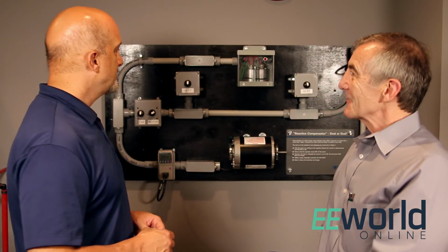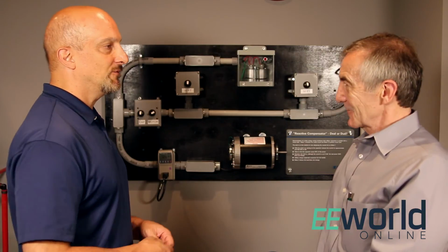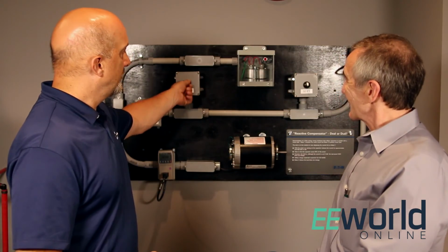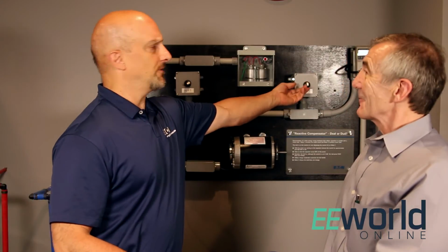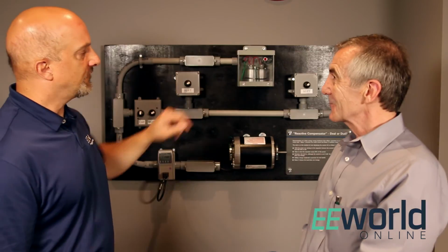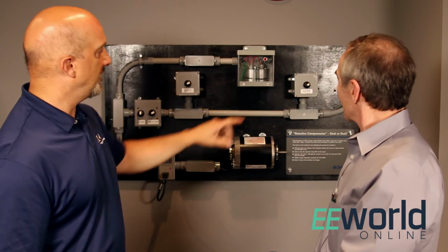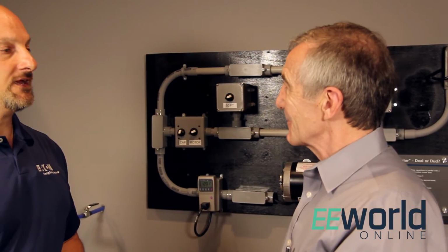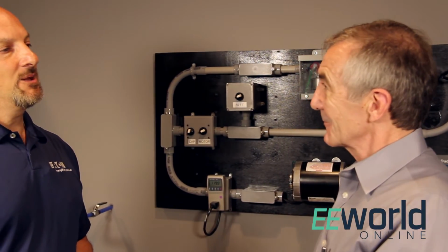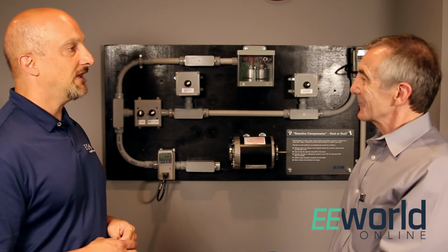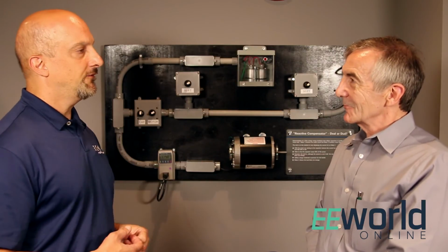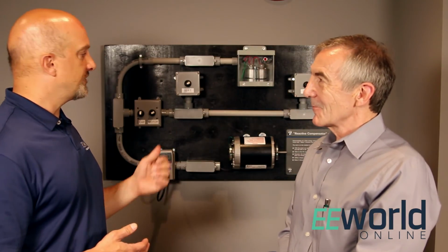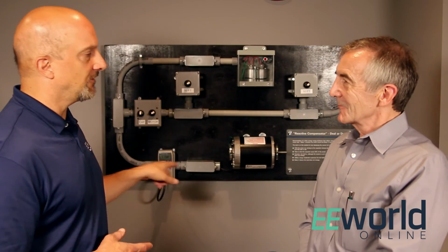And what they'll do is somewhere in their little magic suitcase box they'll have some hidden wire. They'll turn on 50 feet of like 18 gauge lamp cord, maybe another 50 feet, and they'll show a watt difference from the top to the bottom. In other words, from the source coming in to where the motor is. The interesting thing is that's for sure actual watt losses, but they associate that with a real system, and it's so far off scale of what a real system would be that it's not appropriate. But the real losses on a typical system, let's say you had a 100 horsepower motor on a bigger system, 200 feet away from your source, you might have a voltage drop, and you might put a capacitor there, and you might have maybe 1 or 2% savings in losses because of the I squared R losses.